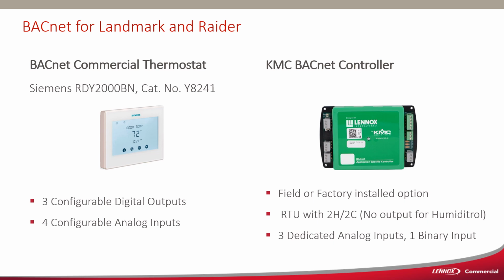If we do have the need for BACnet, we're going to use a BACnet network thermostat. It's a Siemens thermostat, 3 configurable digital outputs, and 4 configurable analog inputs. In the unit itself, we're going to use a KMC unit controller, and this can be factory installed in the unit or field installed. 2-stage heat, 2-stage cool, and there is no output for Humiditrol on this unit controller. 3 dedicated analog inputs and 1 binary input.